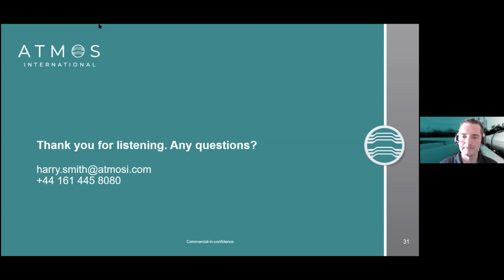Just to check, Harry, did you answer the question about the latest vibration-based leak detection systems? Yes. So, Rakesh? As I said, there is still a lot of research being done into vibration sensors and acoustic sensors, and some fiber optic companies often use acoustic sensors in their detection. The problem being with especially acoustic vibration with fiber optic is it's very difficult to test that it's going to be able to detect a leak. It's very good at intrusion detection and security purposes, but not a lot of pipeline operators are willing to spill fuel onto the ground to test the system.